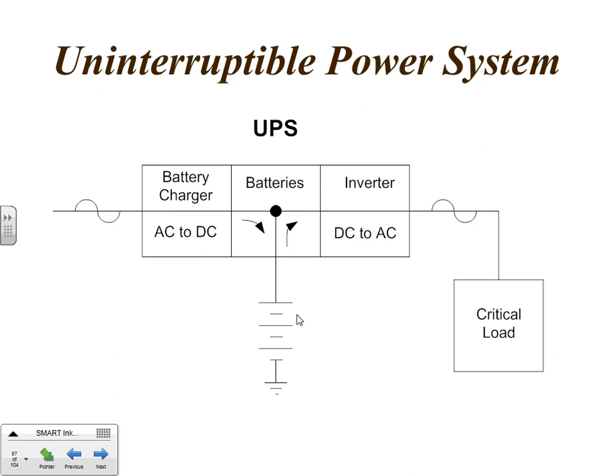What that does, in effect, is it takes the time that critical load is now functioning without utility from the battery, the amount of time we have on a battery, to the amount of fuel we have in the tank out here in the generator set. And then the outage can be any length of time and you'll be good to go.